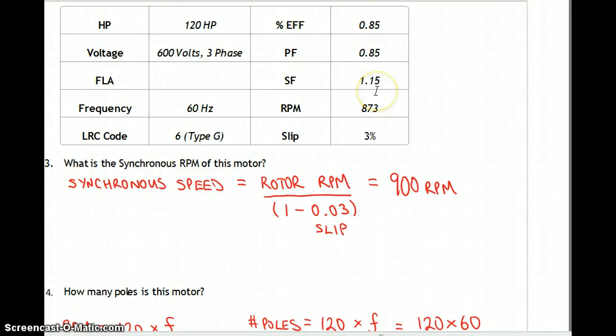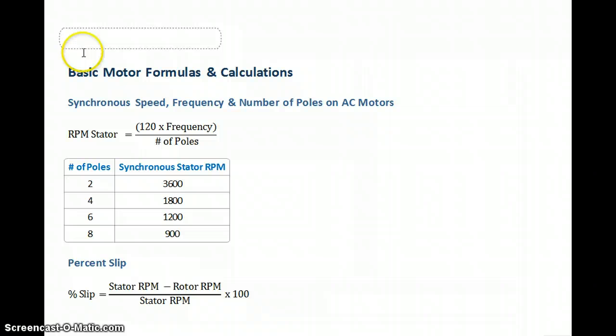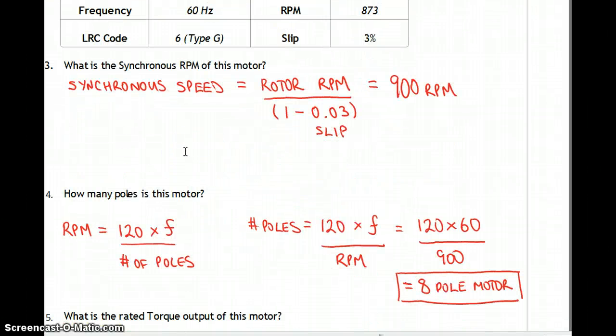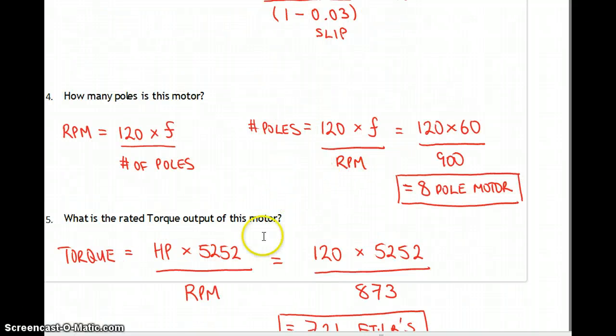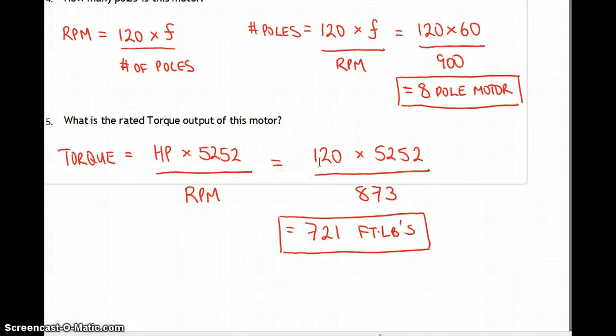Synchronous RPM of this motor: using rotor RPM over 1 minus 0.03 slip gives 900 RPM. The rotor is at 873 RPM, and the closest synchronous speed on the chart is 900 — so it's an eight-pole motor. Number of poles: 120 times 60 over 900 equals 8 poles. Rated torque: 120 horsepower times 5,252 over 873 rotor RPM — this motor punches out 721 foot-pounds of torque.